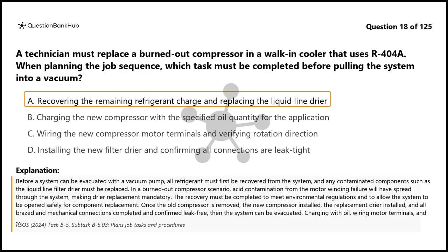for component replacement. Once the old compressor is removed, the new compressor installed, the replacement dryer installed, and all brazed and mechanical connections completed and confirmed leak-free, then the system can be evacuated. Charging with oil, wiring motor terminals, and verifying rotation are tasks that occur after evacuation and during the commissioning phase, not before vacuum pull-down.